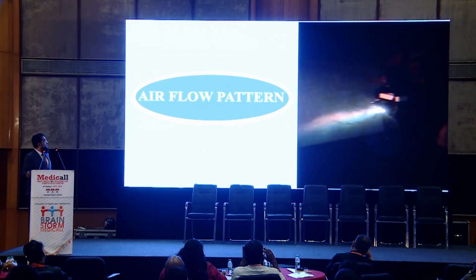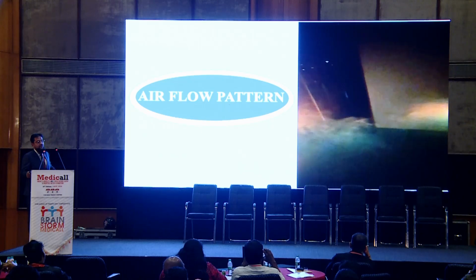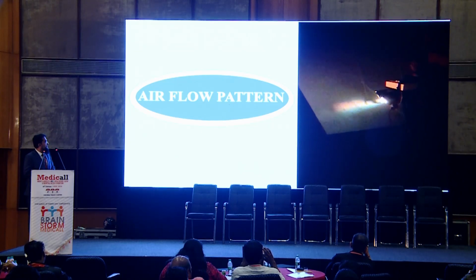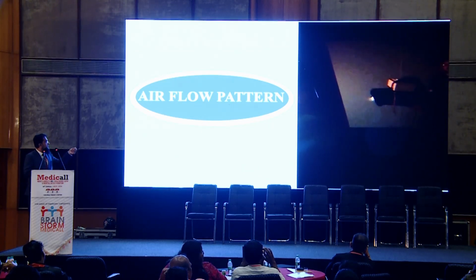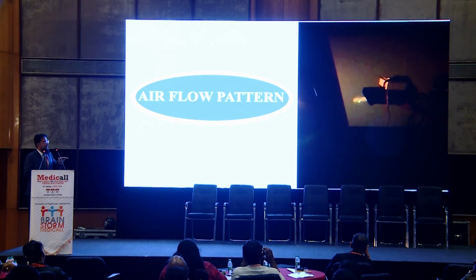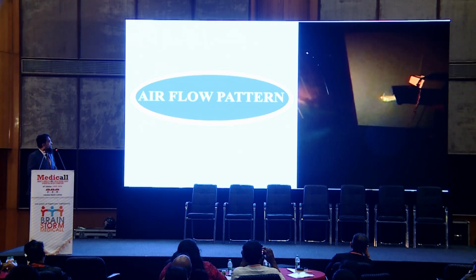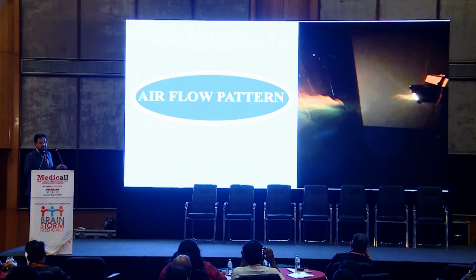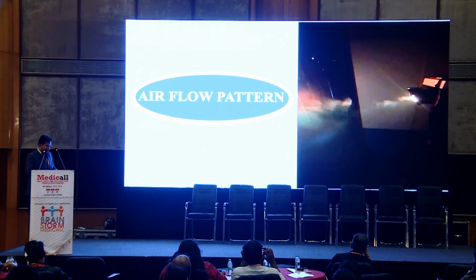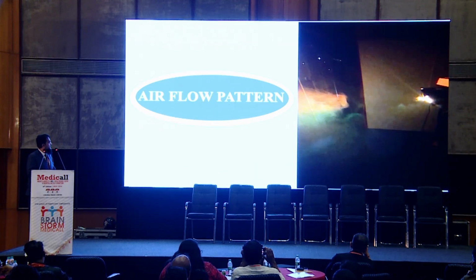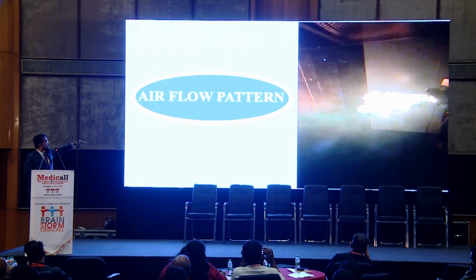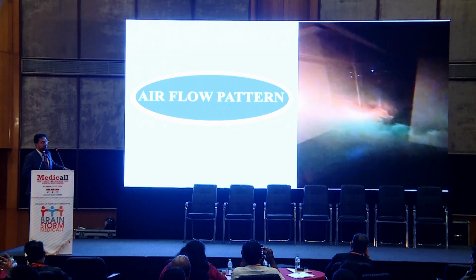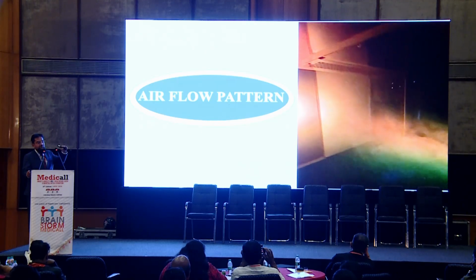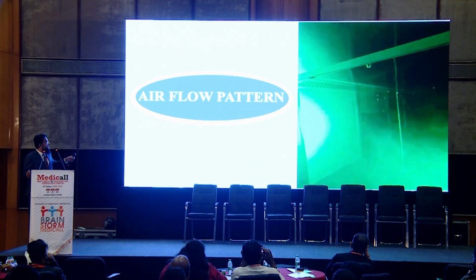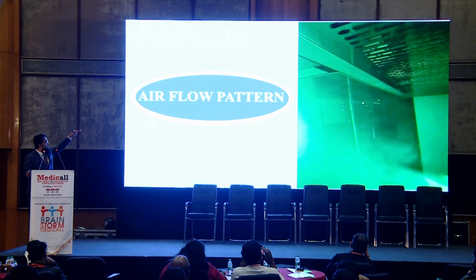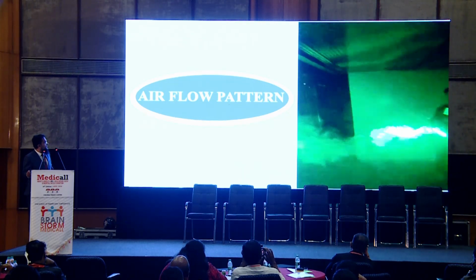I'm showing you how the airflow is maintained, with the smoke test. See now, with this machine we are creating smoke and putting it in the room. To get the visualization with the color effect, we have made it dark, but you can still see how the smoke is not going up, it's coming down. Normally smoke goes up. But when we create the smoke, it does not go up from the HEPA flow, it comes down. Okay, it's not going up.